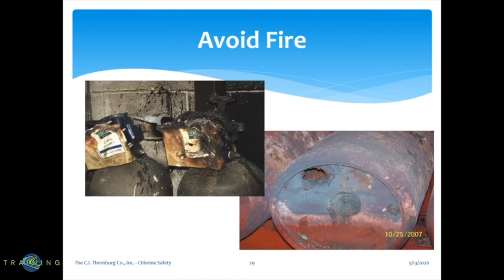This is what can happen with a fire. On the left-hand side you'll see two 150-pound cylinders that were involved in a fire — the fuse plugs melted and they had a 300-pound release of chlorine. On the right-hand side is a ton cylinder involved in a fire where the pressure got so high it blew a big hole in the concave end of the ton cylinder. Just avoid fire as much as possible.